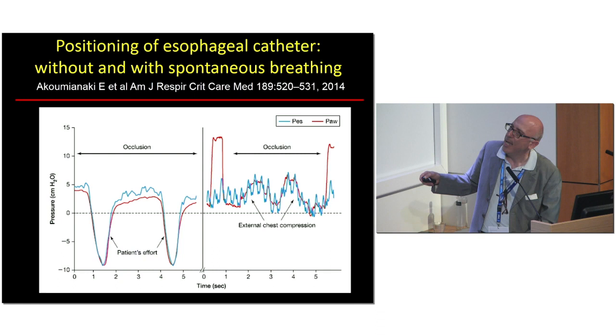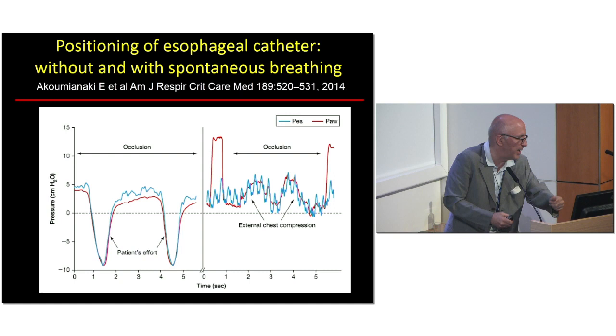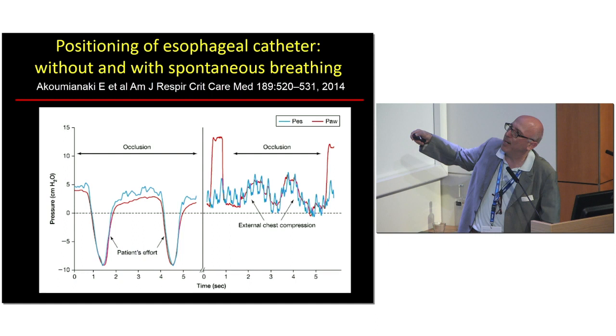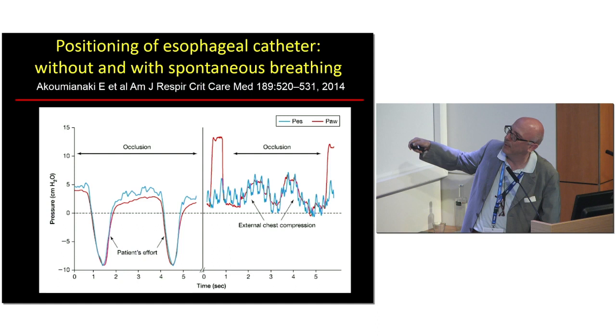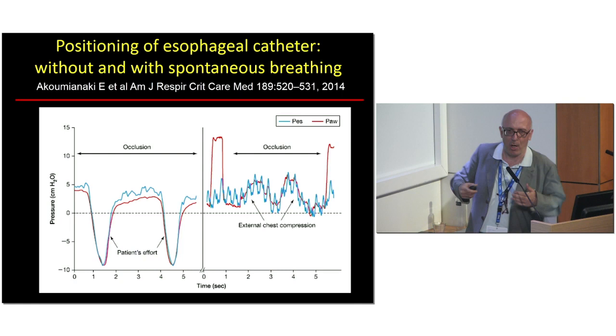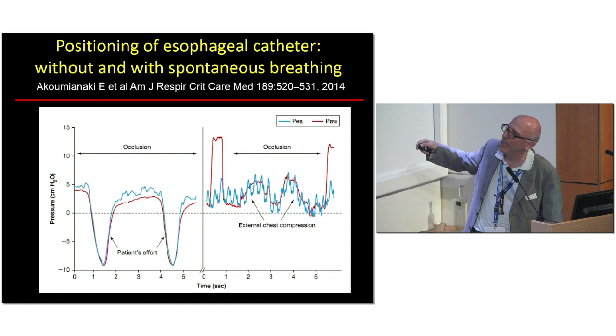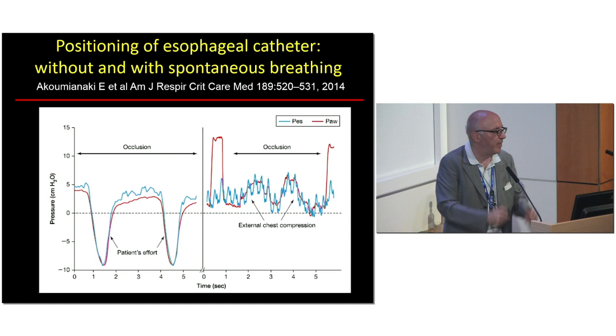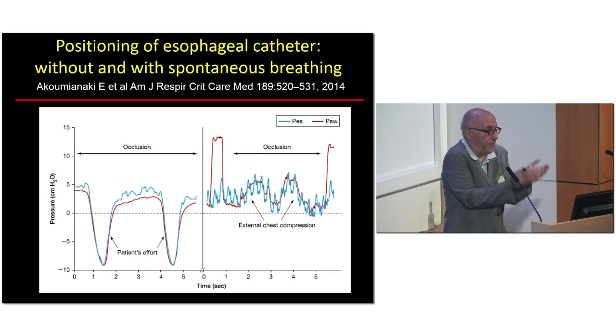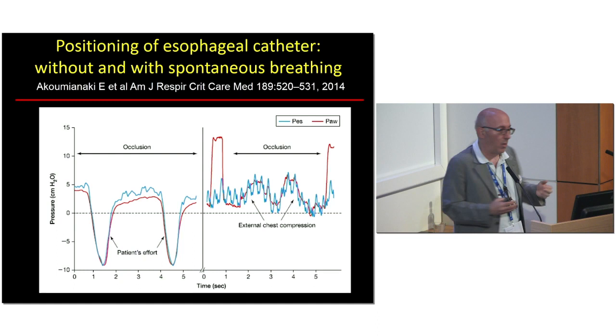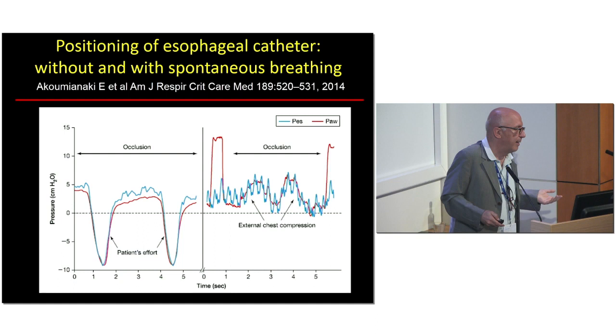If you are in control mechanical ventilation, what you have to do is occlude the airways, wait for expiration, and gently push on the thorax - you increase the pressure in the airways here. You are at the occlusion here, this is the conventional breath. You occlude the airways, push gently on the thorax, and you see the artificial increase in the airway pressure and the artificial increase in the esophageal pressure, and again they should be very similar. These are the two methods to get information on whether the balloon is correctly positioned or not. But again, it's only for that moment - it's for research, because after 2 hours, the patient is moving, or the nurses, or whatever, you don't know anymore what's going on. The balloon has to be recalibrated, the maneuvers redone - very complicated.